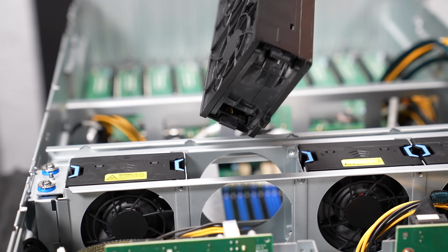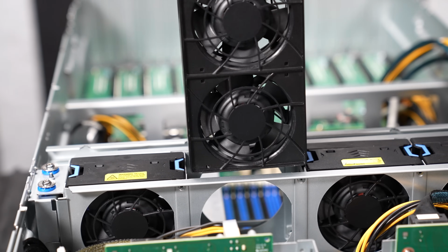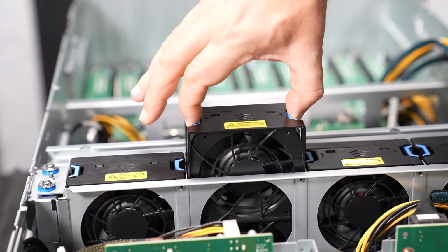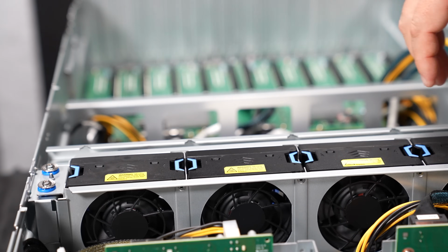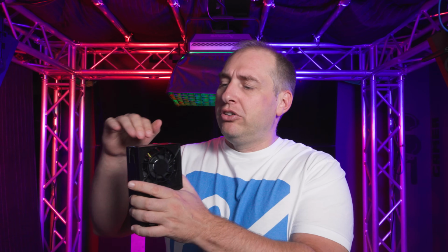There are some systems that only have 1 set of fans that service different GPUs. So if you get one of those systems and you don't have these two fans that can cool something, you only have 1 fan per 2 GPUs. Sometimes what can happen is if that fan fails, all the rest of your GPUs are going to be fine, but you're going to have 2 GPUs that will overheat. And so having a design like this is actually kind of cool. I guess that was kind of a pun too.